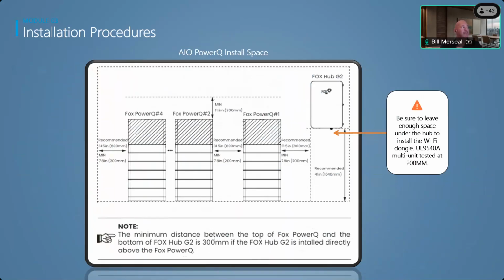If you're going to put the hub right above the inverter, you're going to need at least 300 millimeters, or basically a foot, in between. If you have it any less than that, there's a Wi-Fi dongle that comes with the hub for communication, and that dongle does stick out on the bottom. You can move that dongle to the left or right of the hub. However, from an ease standpoint, if you've got the room, try to be 12 inches from the bottom of that to the top of your inverter.